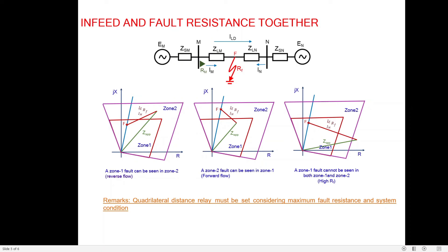Even though the quadrilateral characteristic has higher fault resistance coverage, it might still fail to capture the fault inside its boundary. Increasing fault resistance coverage risks load encroachment — during high loading conditions the load impedance may fall inside the fault zone, causing relay mal-operation. This topic of load encroachment will be discussed separately. In summary, this session covered the effect of pre-fault power flow magnitude, pre-fault power flow direction (import or export), and fault resistance on distance relay performance.